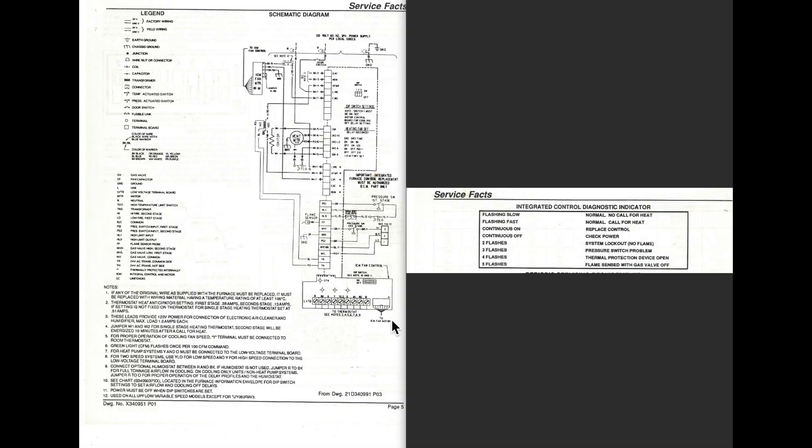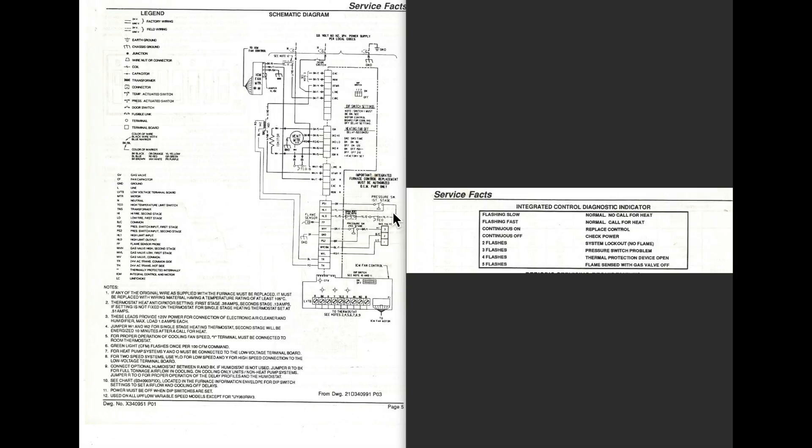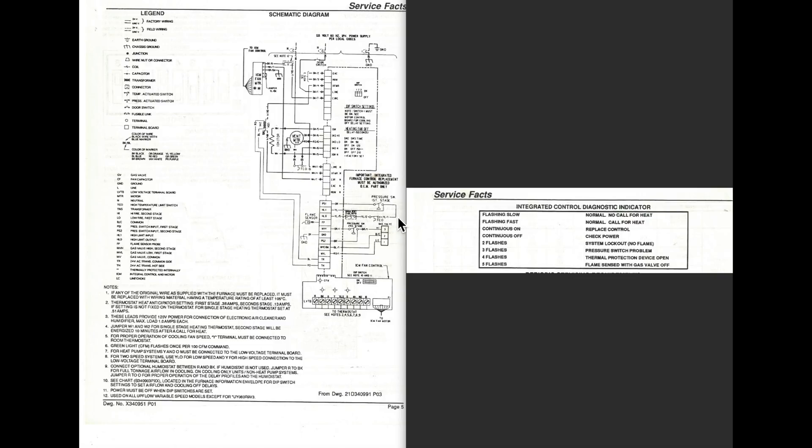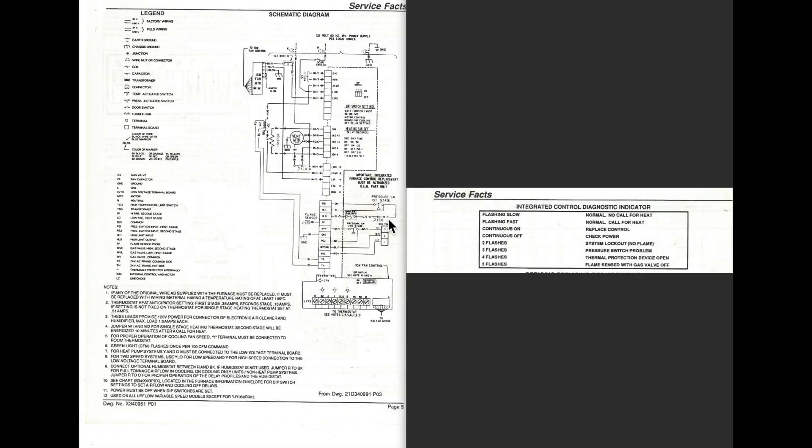So let's go through a quick sequence of operation of this thing. If we have fast flashing, then as soon as that comes on, the board's going to check the pressure switch and say, is this pressure switch open or closed? If it's closed, it won't come on. That's safety. If it's open, inducer comes on, increases the pressure. The pressure switch closes. This does two things. One, it feeds back into the board and tells the board that the pressure's okay and we're ready to go. The other wire here goes over to the limit switches and checks to see if they are closed. If the board sees that these switches are closed, then it continues. Both pressure switch and limit switches have to be closed for this to continue with the sequence.